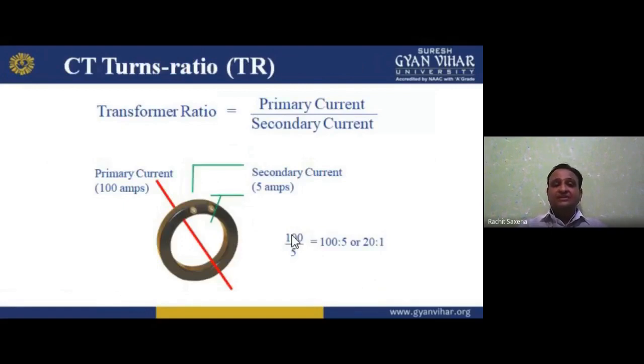Now CT, what is CT? CT is basically the turn ratio. The turn ratio is given by the primary current over the secondary current. My dear students, the CT is the current transformer, and a current transformer always has a construction similar to the step-up transformer. In a step-up transformer, the primary winding voltage is lower compared to the secondary winding voltage, but the primary winding current is higher compared to the secondary winding current. So we want to step down the current but step up the voltage.